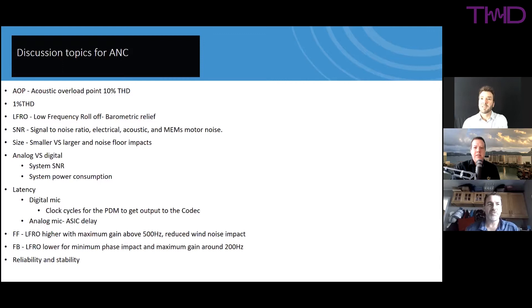Simon raises that microphones operate below their fundamental resonance for a flat response. For a typical 4 mm electret, resonance is around 4–5 kHz. For MEMS it is much higher. Eric confirms MEMS resonances are well above 10 kHz — most of Knowles' newer products are in the 35–42 kHz range, driven partly by voice applications.